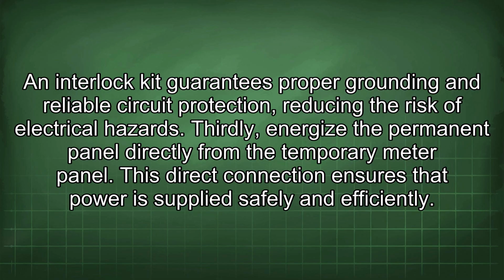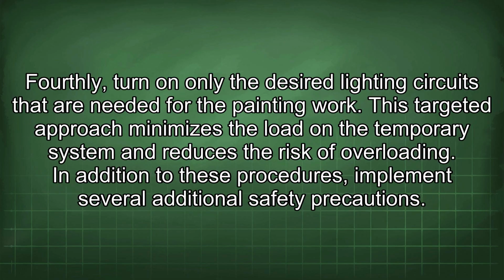Thirdly, energize the permanent panel directly from the temporary meter panel. This direct connection ensures that power is supplied safely and efficiently. Fourthly, turn on only the desired lighting circuits that are needed for the painting work. This targeted approach minimizes the load in the temporary system and reduces the risk of overloading.